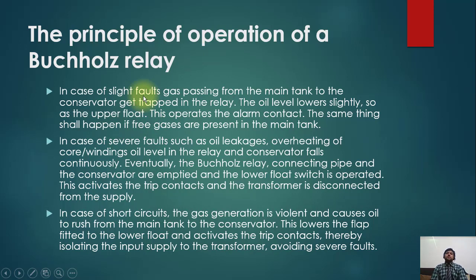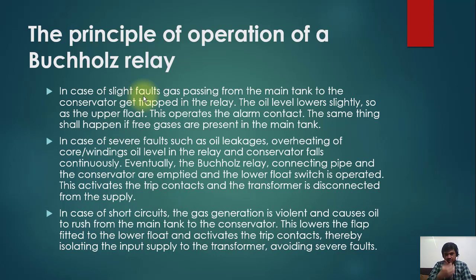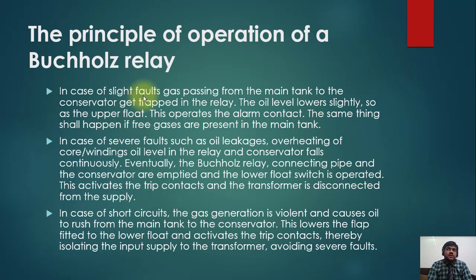Now let's discuss in detail with diagrams how the Buchholz relay operates. In case of a slight fault, gas passes from the main tank to the conservator and gets trapped in the relay, causing the oil level to drop slightly. This operates the upper float, which activates the alarm contact. This can also happen when free gases are present in the main tank — for example, when a transformer is newly installed and dehydration is being performed, trapped gas may take time to release and trigger the Buchholz.